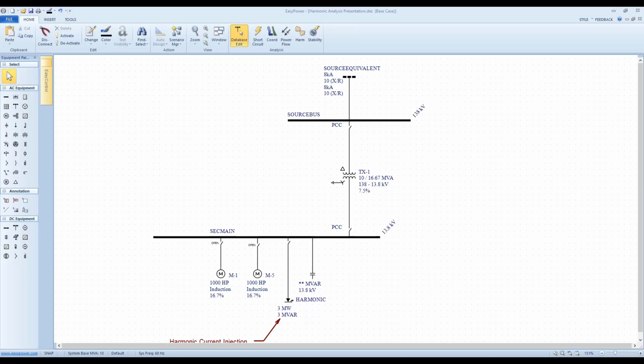In my practice, if it's two 6-pulse rectifiers operating in 12-pulse mode through a delta-Y transformer, I just model it as a harmonic current injection and not concern myself with the phase angles of those various harmonics. There are locations on the web, if you look for it, where you will find those phase angles, but I think it's an exercise that's not necessary. The result is, if it's two 6-pulse devices operating in the 12-pulse configuration, then model the 12-pulse harmonics. That'd be just 12N plus or minus 1, right? The harmonic numbers. So that's been my practice, rather than trying to get into the inner workings of two 6-pulse devices operating in a 12-pulse fashion.